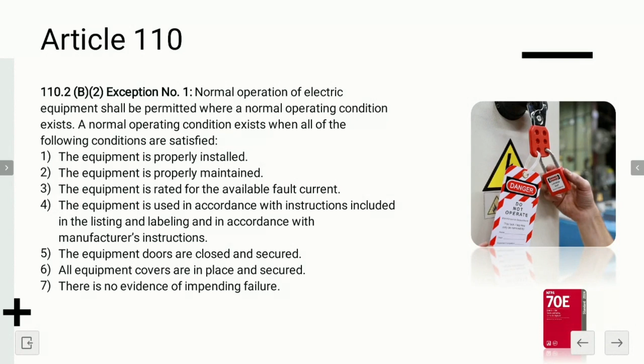We're using the equipment in accordance with the manufacturer's instructions, the listing and labeling, things like that. Okay. So again, properly installed means it's been installed according to the National Electrical Code. Take a few steps back, a couple of deep breaths, and just look at it. You know, this is third year. You probably got a good idea if it's been installed correctly. Or properly maintained means that it's been maintained in accordance with the manufacturer's recommendations and what's called the NFPA 70B. A lot of people don't know that this even exists, but there is a code for maintenance. That's called the NFPA 70B.